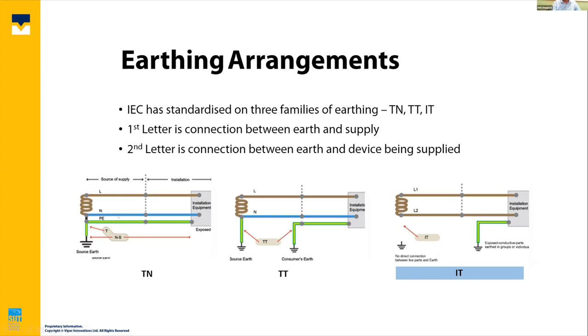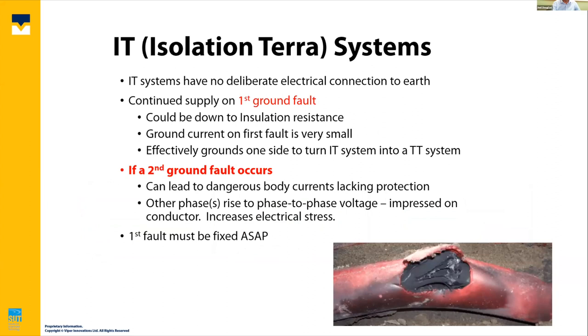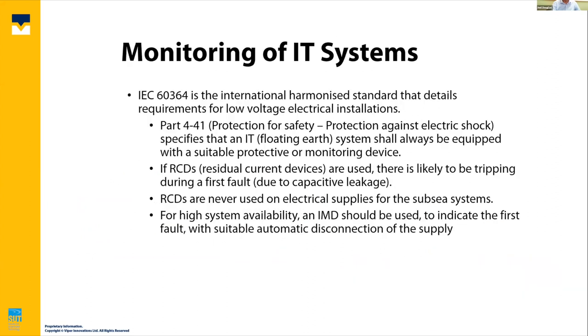On the TN system in your domestic household, you know that if you touch the neutral, it's already at ground potential. You do not get an electric shock. However, if you touch the live conductor, you most certainly do get an electric shock. Hence, the domestic supply is not as resilient or tolerant to individuals touching it and not getting an electric shock. So, having described why IT systems are important, we now need to look at the legislation.